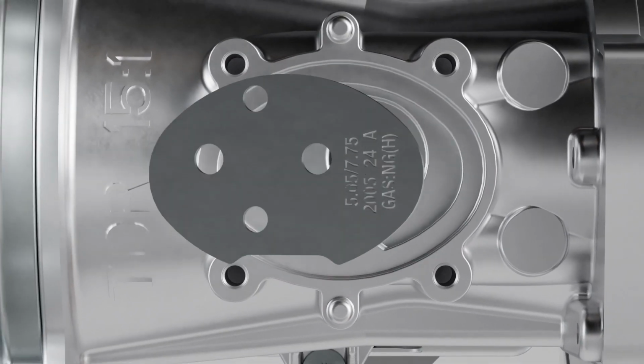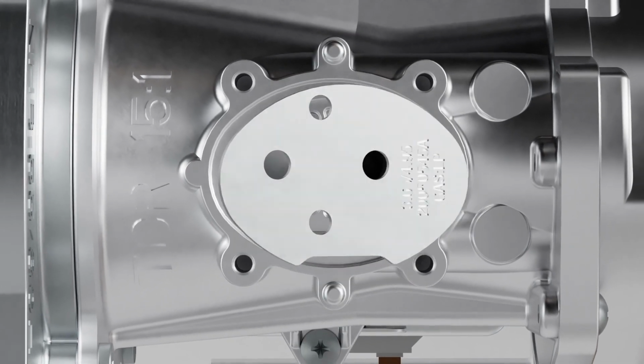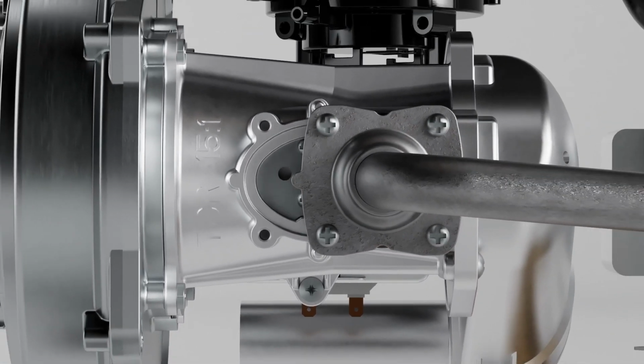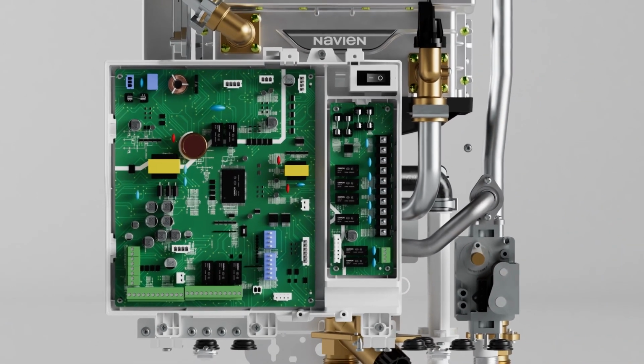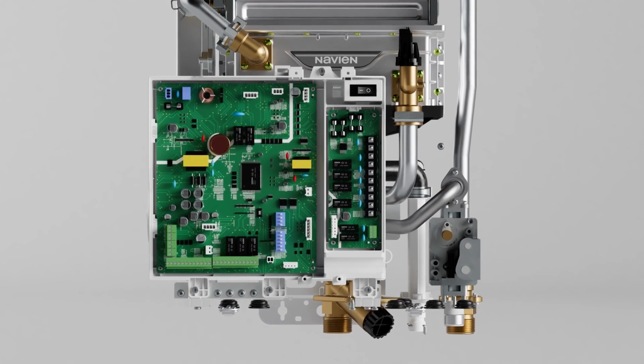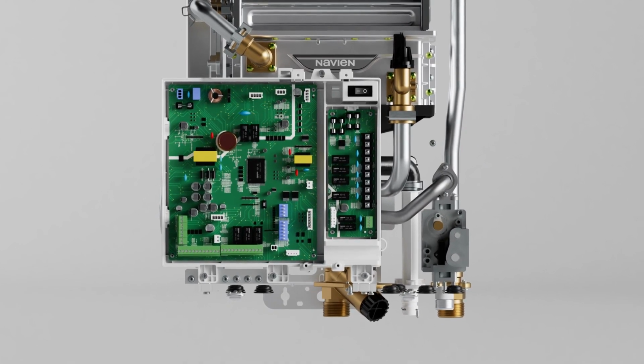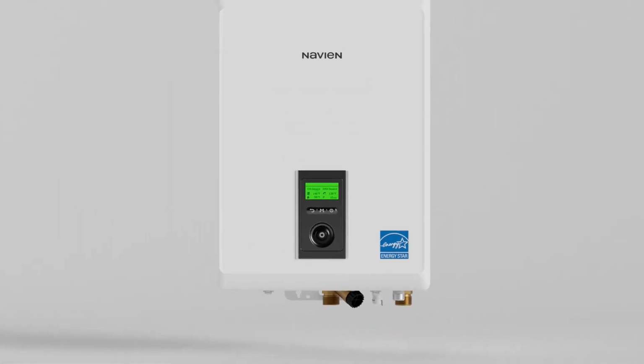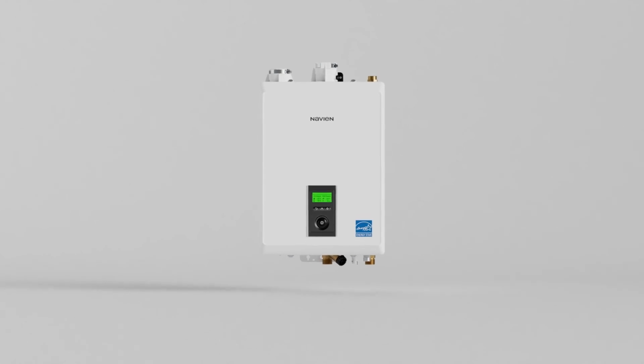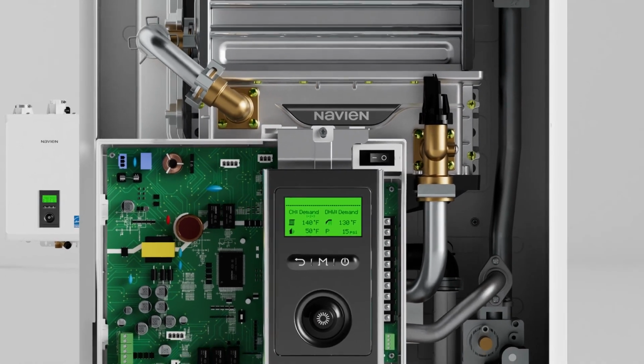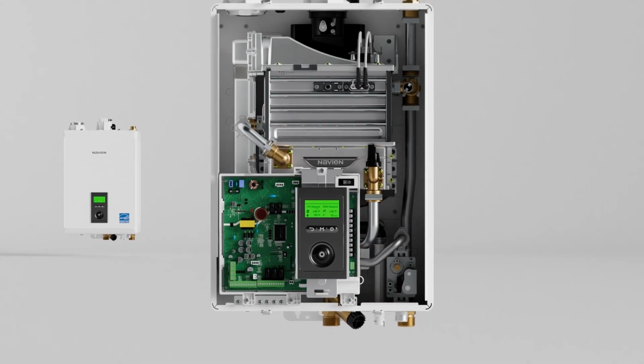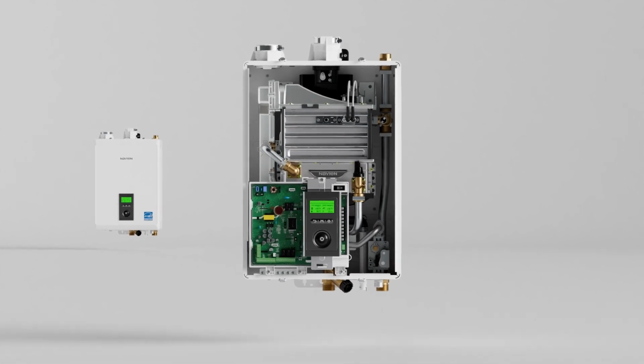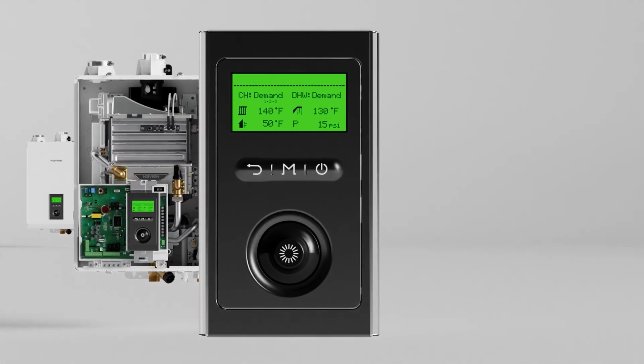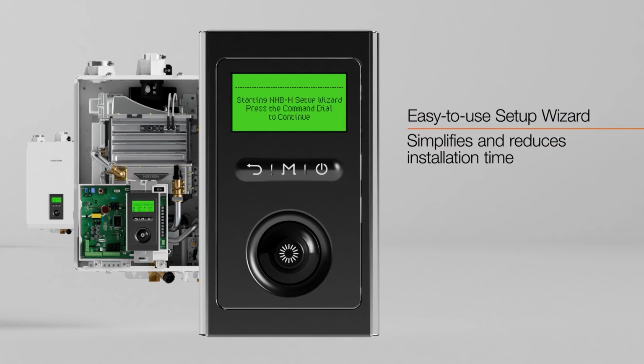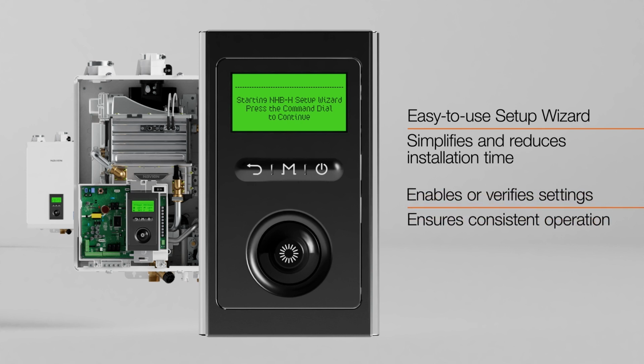Field gas convertibility is made easy with conversion kits for natural gas, propane, and high altitudes up to 10,100 feet included with every boiler. All NHBH models have integrated hardware and software to connect a boiler pump and up to 3 zone pumps or 3 zone valves. The NHBH Advanced Front Panel Controller features an intuitive multi-line LCD display and a command dial for quick setup and easy access to data, diagnostics, and troubleshooting. The control also includes the option to utilize one zone for an indirect tank control, providing domestic hot water capability. The easy-to-use setup wizard simplifies and reduces installation time. It also enables or verifies important settings, ensuring consistent operation.